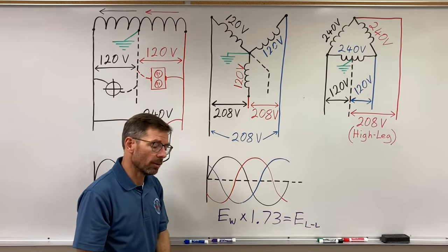The high-leg delta system is mostly an older system — utilities in many areas are not installing these as new systems. If you have equipment that operates on 240 but your new service doesn't have 240, come back for another class and we'll talk about how you can boost your 208 up to 240, which would require a separate type of transformer.